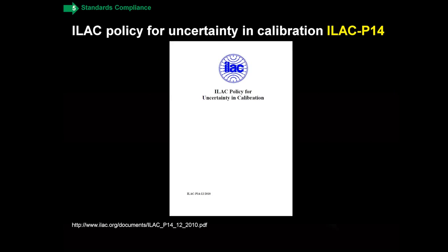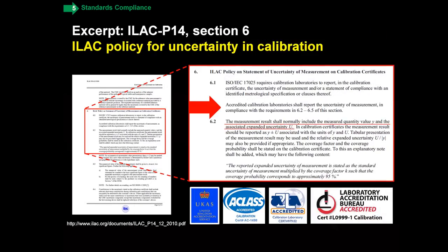Finally, I want to talk about the ILAC policy for uncertainty in calibration — ILAC P14. Notice that this is a policy document, so it's very strong: it's not just a guide, it's a policy. This is what dictates the rules that accreditation bodies have to follow. Paragraph six says that accredited calibration laboratories shall report the uncertainty of measurement in compliance with the requirements. The bottom line is: everything we talked about in section three of the series — the measurement uncertainty — you must include and report that if you want to include the accreditation symbol on the calibration certificate.